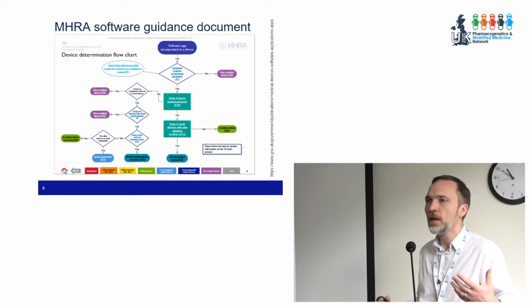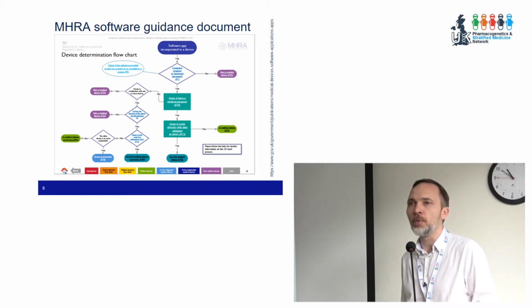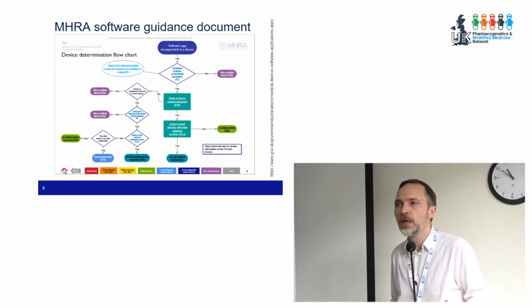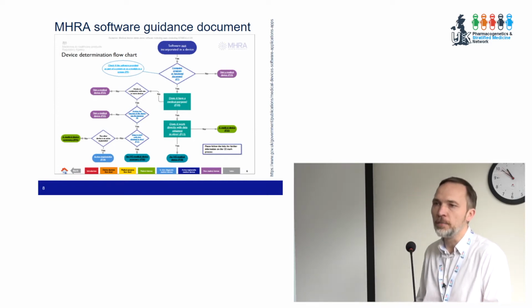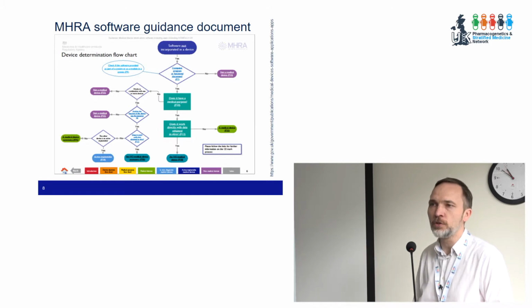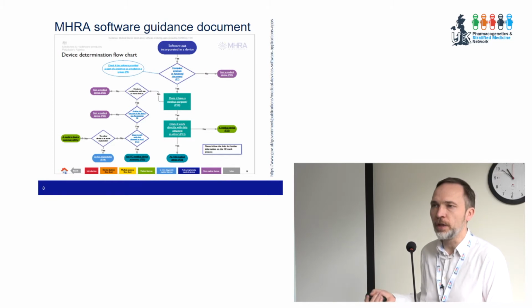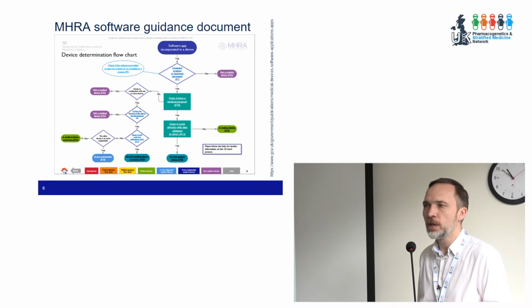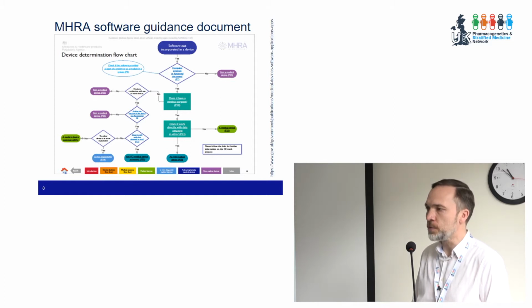I know that's not very clear, but those of you who've seen on our website, and the link is just here, the software, it's an interactive PDF, so you can go through the flow chart, and it'll help you decide from a directives point of view, not from a regulations point of view, whether your software is not a medical device, whether it's a medical device or a medical device accessory, whether it's an IVD or an IVD accessory. And that flow chart, we've got some really good positive comments coming back from it, so I'd really like people to challenge it with some more complex bits of software.